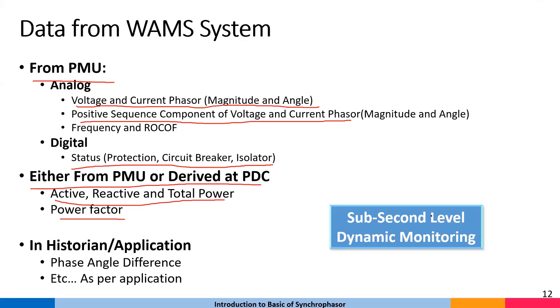You can also get digital status, like protection, circuit breaker, and isolator status. This device data comes from the synchrophasor device, and at the control center, we have a PDC, phasor data concentrator. Its job is to time-align all the data from different phasor measurement units located in the field. At the control center level, you can also calculate power factor, active power, reactive power, and so on.